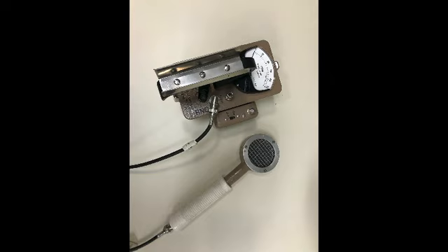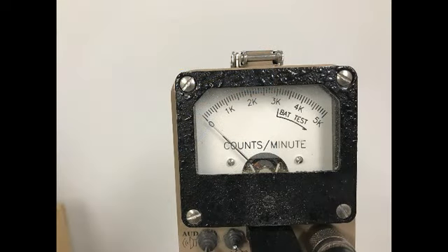So one is a Geiger-Müller counter. These are extremely sensitive, so they could be used to find a lost seed, for example, but they don't give you a measurement of the exposure in millirem per hour. They're typically calibrated in count rates, counts per minute. And so you might use this first to find a hot spot, an area where you need to look further.